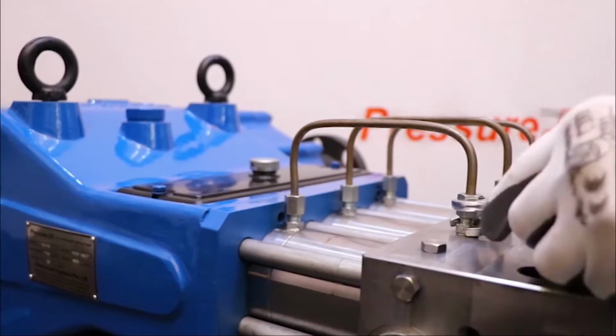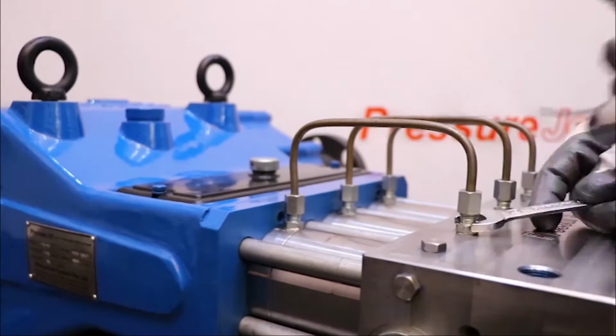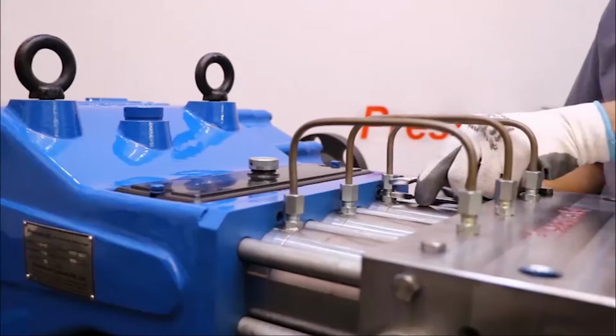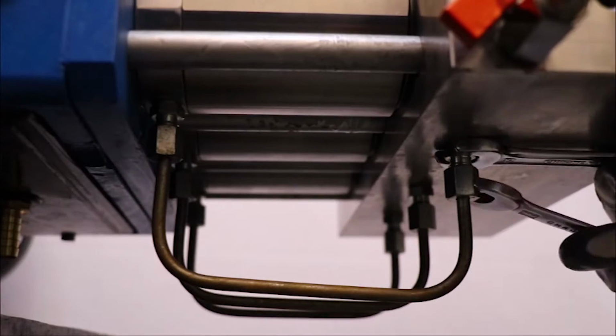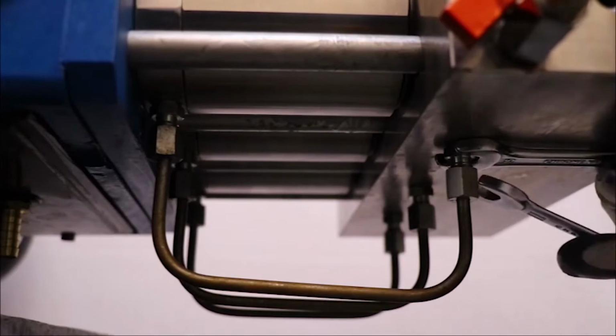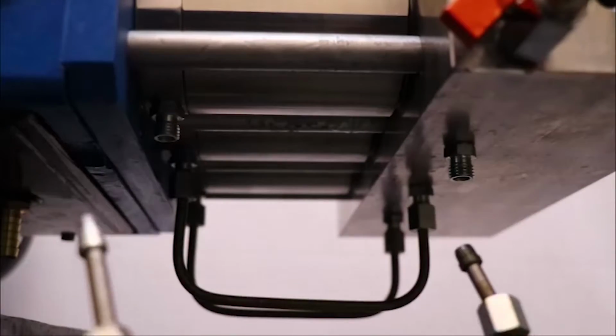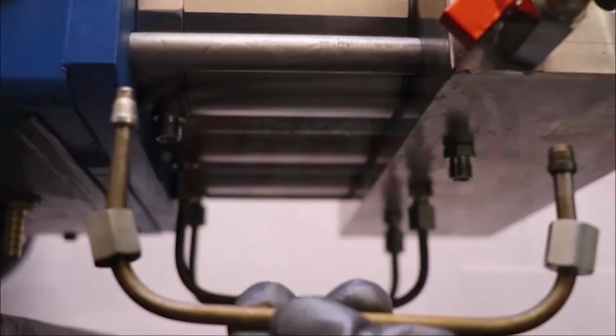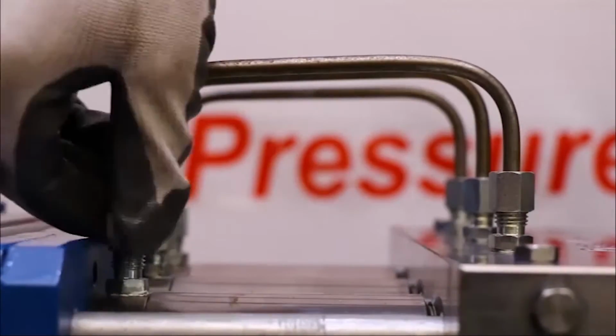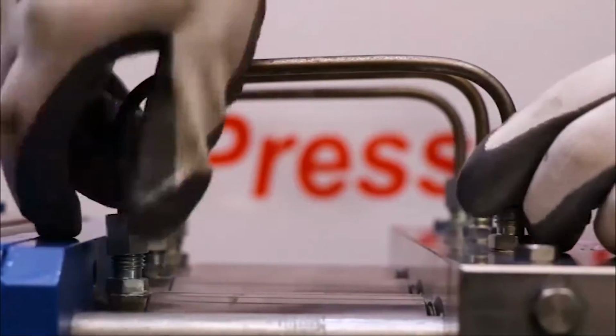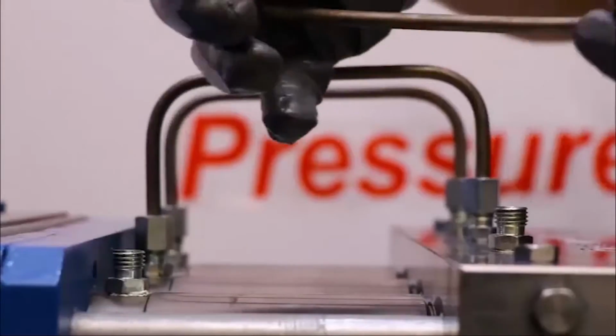Unscrew top side ferrule connection of cooling pipes. Also unscrew bottom side ferrule connection using spanner and remove all bottom cooling pipes. Same as bottom, remove all 3 cooling pipes from top side.